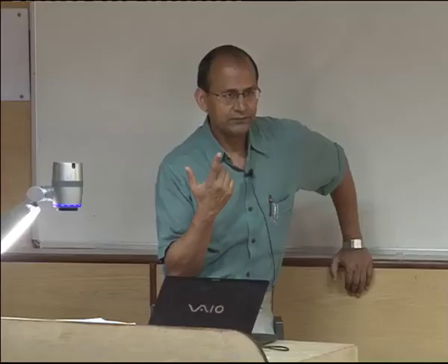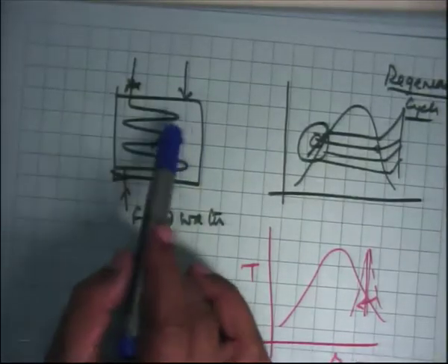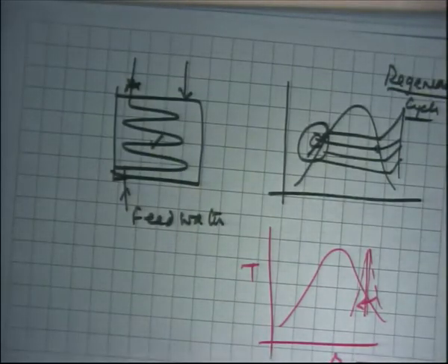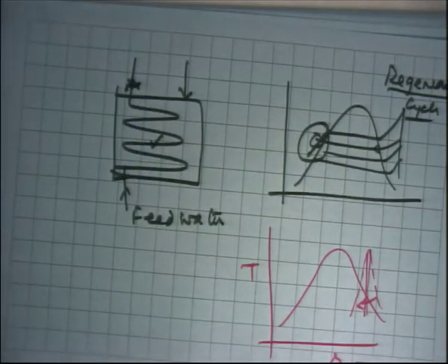So, in such subcritical boilers, the number of feed water heaters usually is 7, 6 closed feed water heaters and 1 deaerator. Okay. A deaerator is where the feed water and steam are not distinctly separated like this, but you have the feed water here and the steam is mixed with it. Okay. And the dissolved gases can escape and you have a vent. Okay. So, that is why it is called a deaerator.